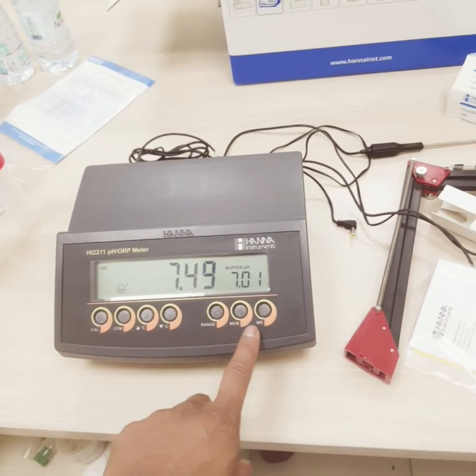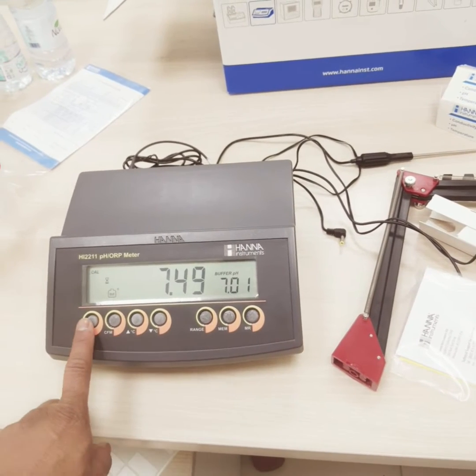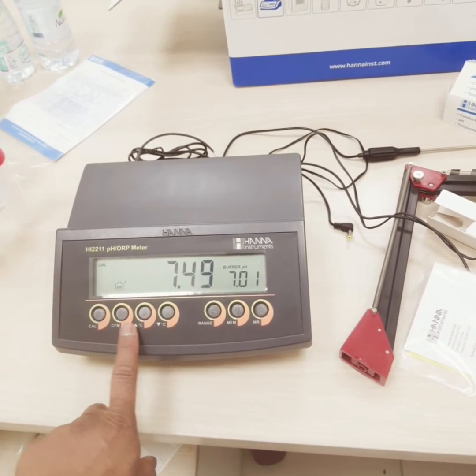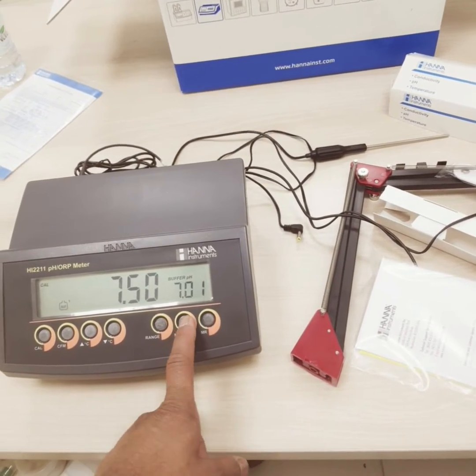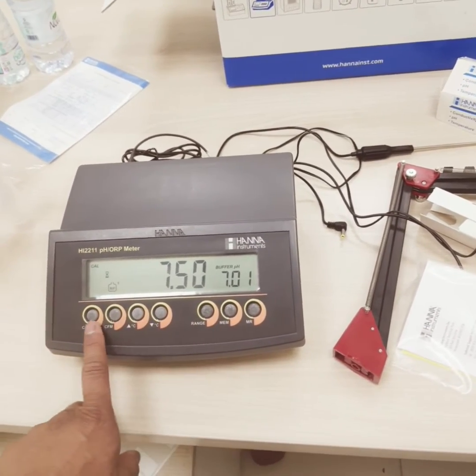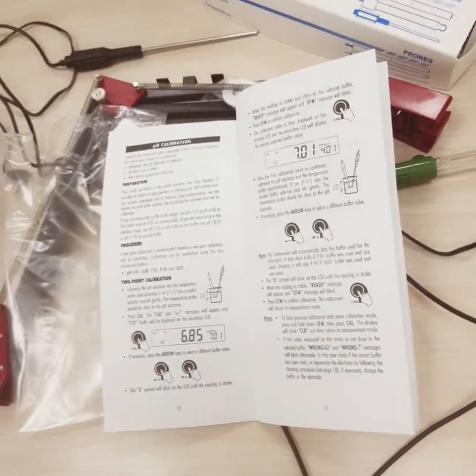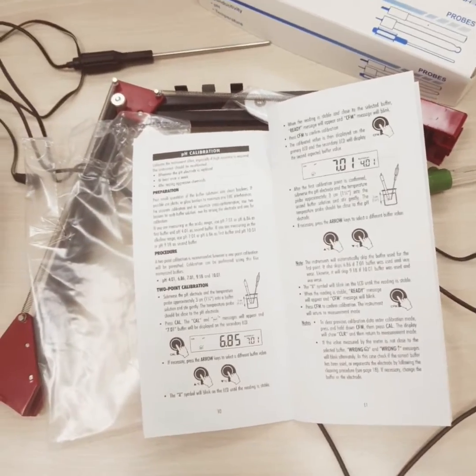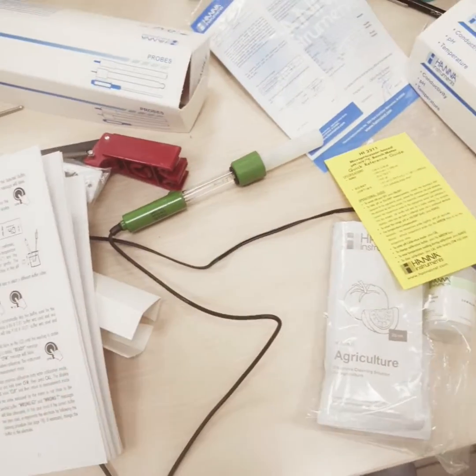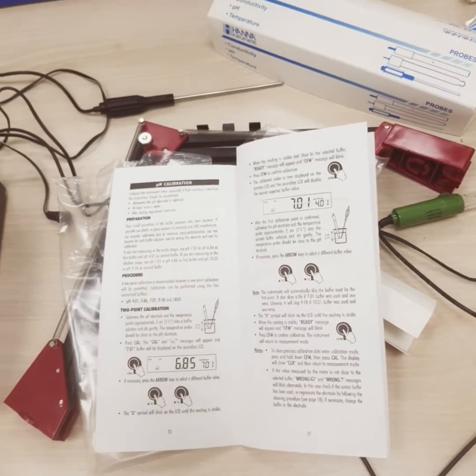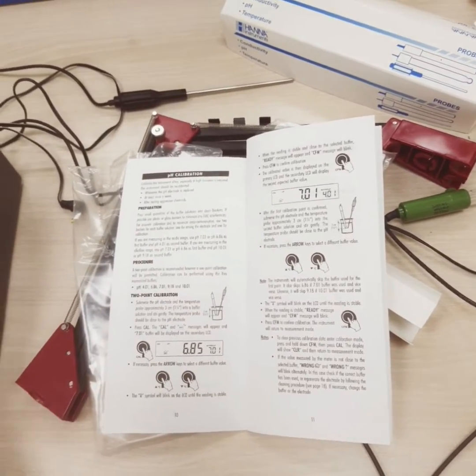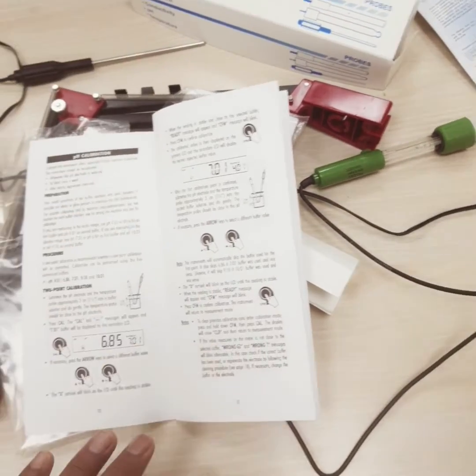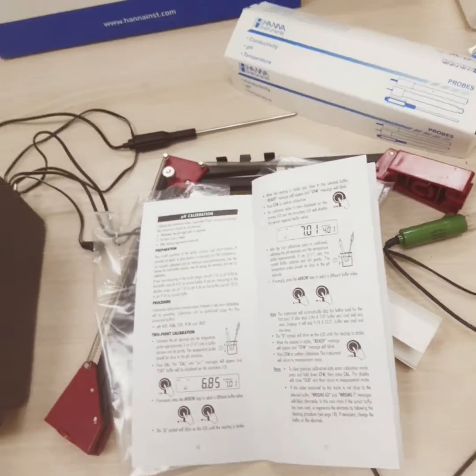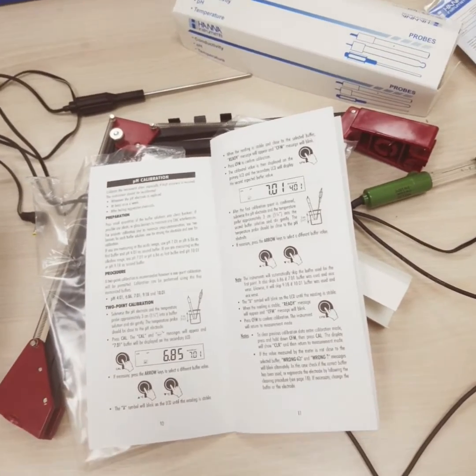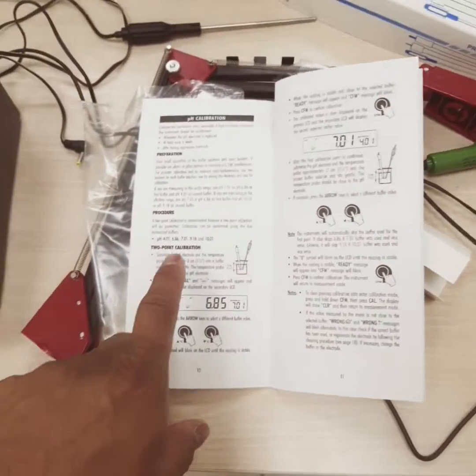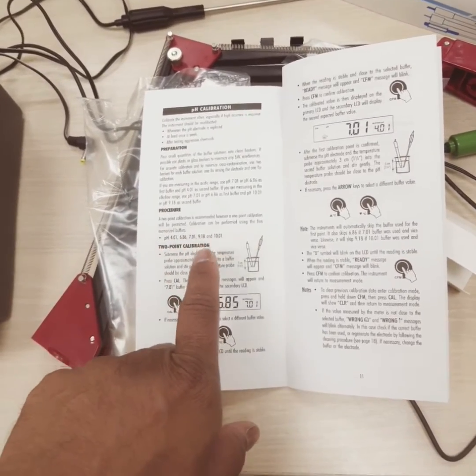Now it says you have to start calibrating. Okay, before starting the calibration, you have to make sure your electrode is replaced. So here there is no point of replacing the electrode, since the electrode is new here, and it should be checked once a week. And if you have tested this for aggressive chemicals, then you have to clean it. So these are all troubleshooting procedures. And also, we have to do 2-point calibration, 1-point calibration. So we are going to do the 3-point calibration, so using pH 4, 7, 9 or 10.